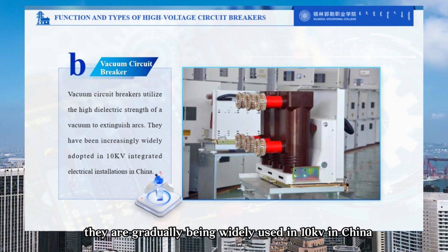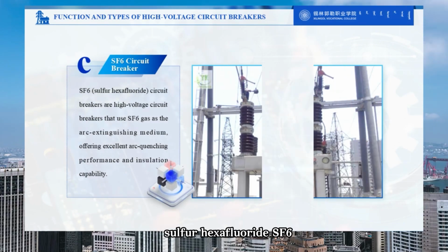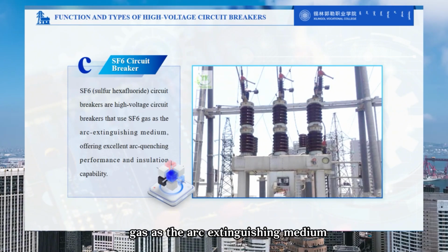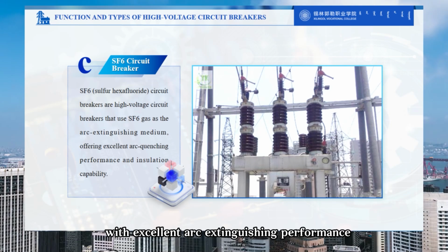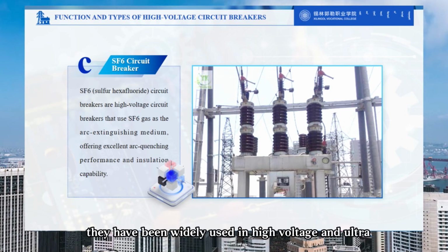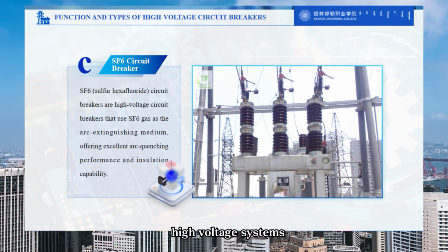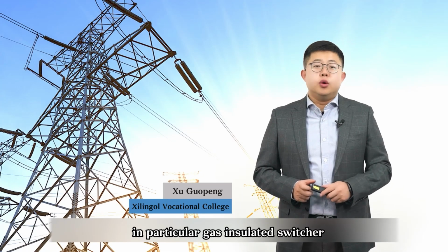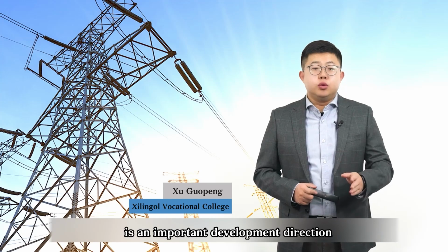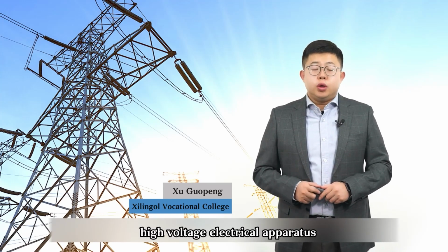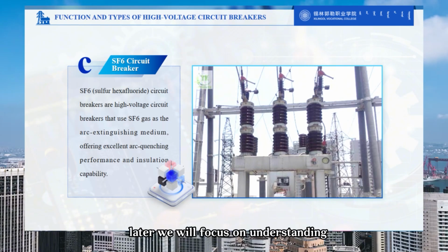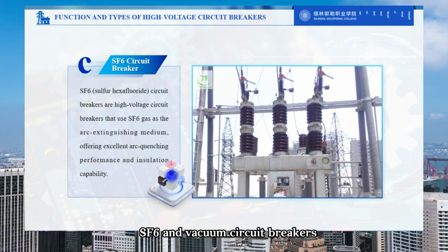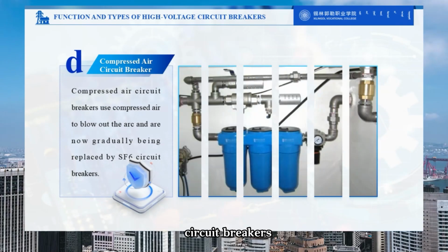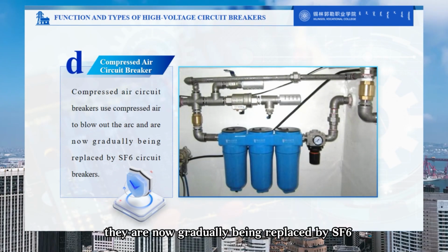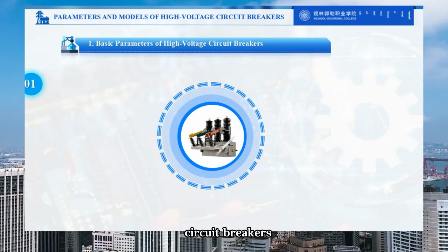Currently, they are gradually being widely used at 10 kV in China. Sulfur hexafluoride, SF6, circuit breakers use SF6 gas as the arc extinguishing medium. They are high-voltage circuit breakers with excellent arc extinguishing performance and insulation capability. They have been widely used in high-voltage and ultra-high voltage systems. In particular, gas-insulated switchgear, GIS, centered around them is an important development direction for high-voltage and ultra-high voltage electrical apparatus. Later, we will focus on understanding SF6 and vacuum circuit breakers. Compressed air circuit breakers use compressed air to blow out the arc. They are now gradually being replaced by SF6 circuit breakers.